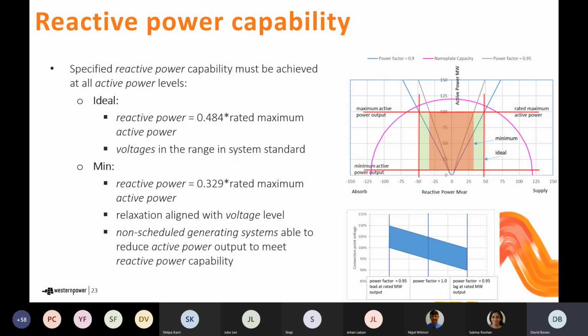So if you're meeting the ideal standard, you need to be able to deliver that reactive power output for any voltage within the range specified in the system standards. The minimum standard, on the other hand, allows for some relaxation of the requirement at different voltage levels. And that relaxation is indicated by the diagram that we've got on the bottom of the page.